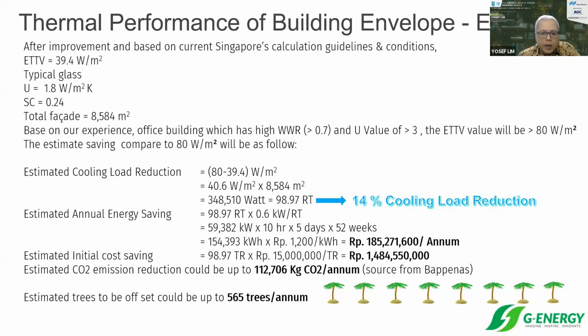So if we compare based on that condition, what happens if we're able to reduce the ETTV value from 80 watts per square meter to 39.4 watts per square meter? That's a reduction of around 40 watts per square meter, multiplied by the surface area of the facade. We're able to reduce the cooling load by around 98 tons of refrigeration, equal to 14% of the total building cooling load. 14% may not sound big, but if we calculate in more detail, we'll be surprised by the savings.